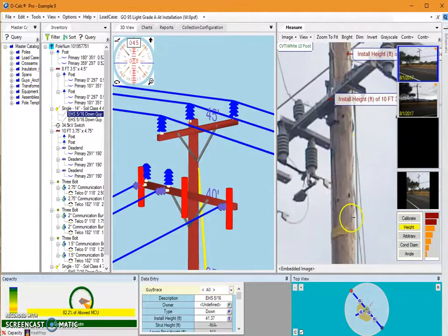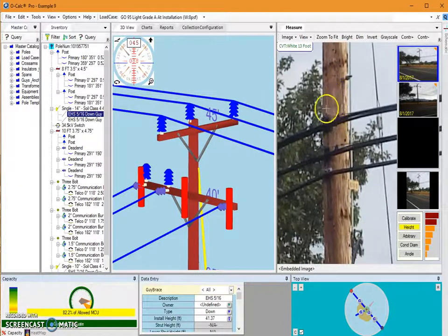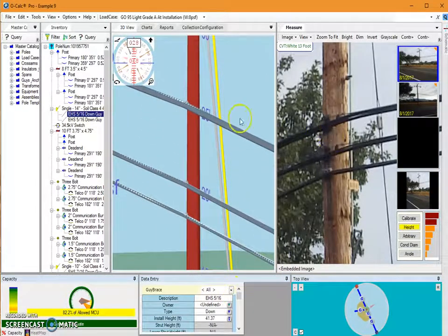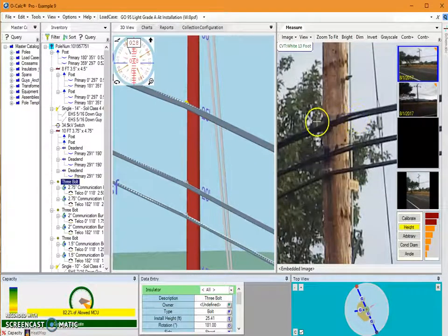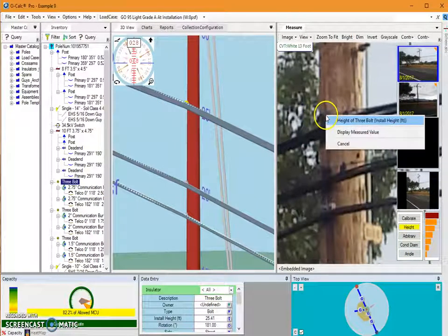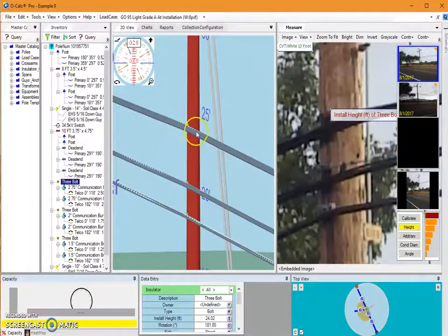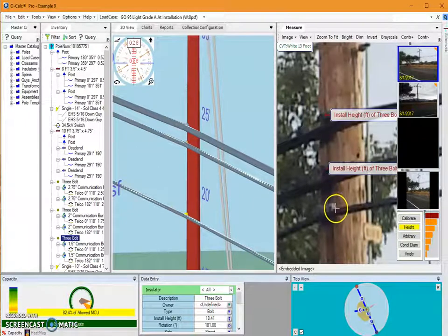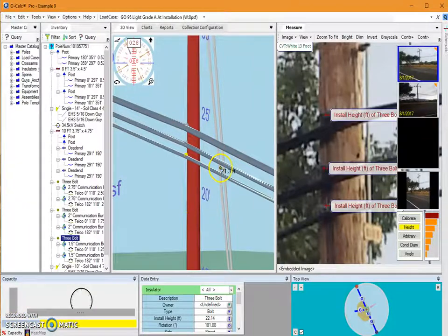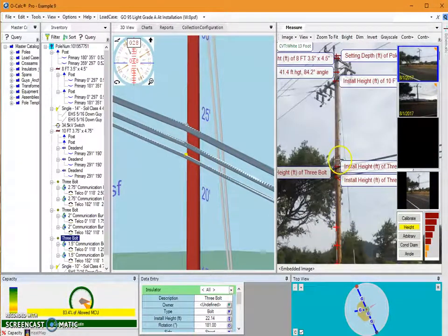Next we're going to continue moving down our pole until we get to our communication section. Moving down in my 3D view, I see three communication bundles and the spacing in my 3D view model isn't quite the same as in my Measure window. To set the attachment heights we're going to use the different through bolts. I select the top one, zoom in to where that through bolt is, set the height, and it moves down in the 3D view. We do the same process to the other two to snap their heights into more accurate positions.